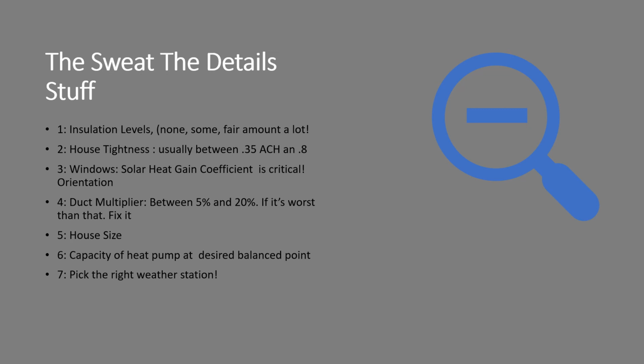Duct multiplier is critical. Fifteen to 20% is really a pretty good estimate. I know many of you don't do duct leakage tests, and that's perfectly okay, but I urge you to do what I call the Homer Simpson duct leakage test. That's where you turn the system on and let it run for a while, so you're either heating or cooling, and go around to each register. Is there conditioned air coming out of each register? If not, go find out why. It might be a disconnect or it could be a closed damper.